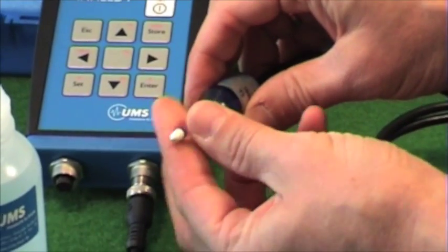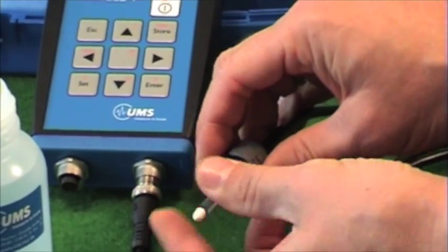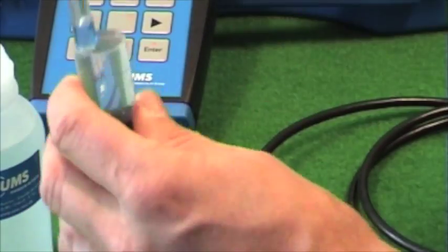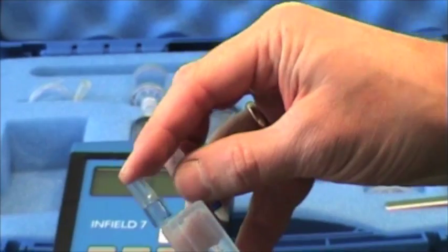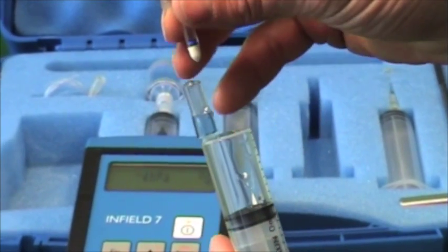To disassemble the shaft, hold the sensor body and turn off the shaft counterclockwise. Remove all bubbles and push the syringe over the ceramic end.